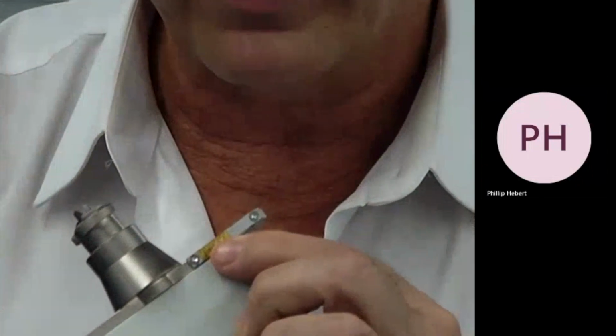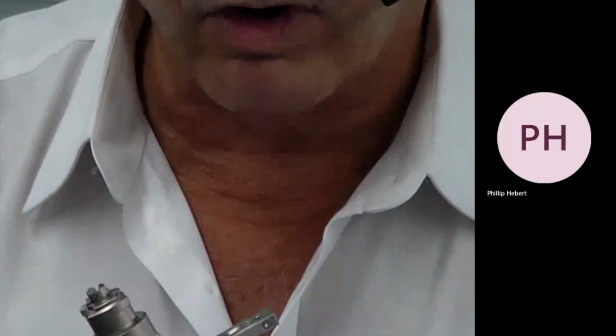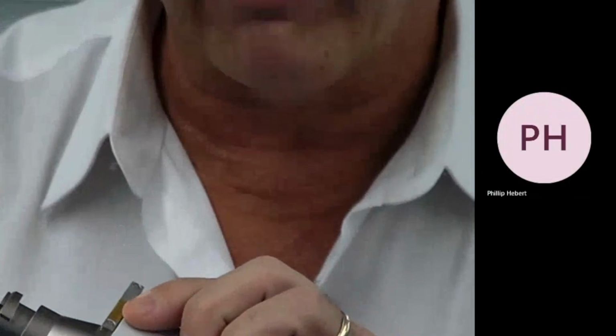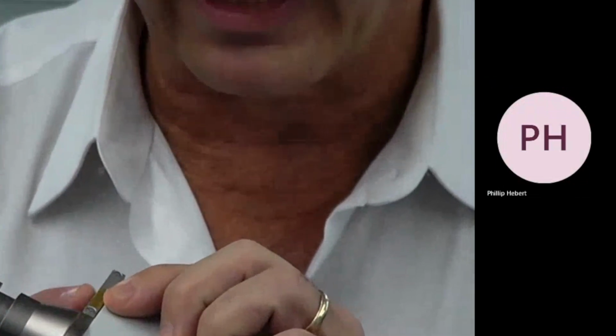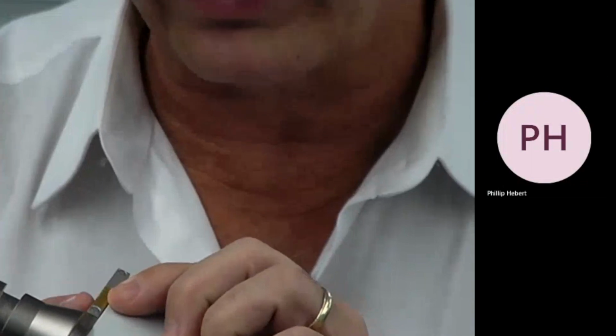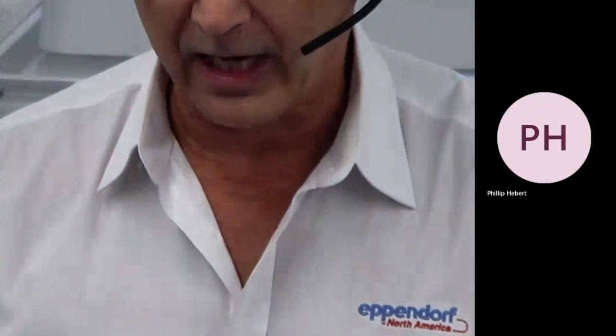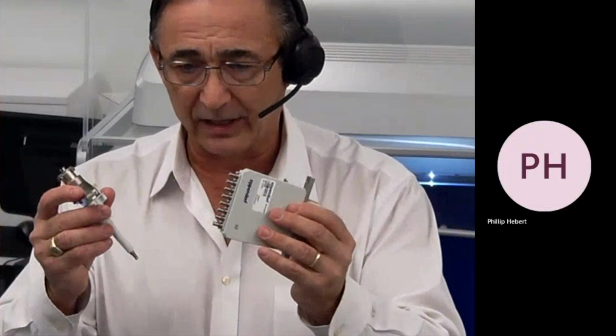And so it'll go and look at this. It will look here at the chips. There's little chips here. The chips actually identify the serial number of the tool, the last calibration date, and it keeps a running tally of the number of pipetting strokes since the last calibration date, and it will let you know if you are out of calibration. If you've gone more than a year or 200,000 pipetting strokes, it pops up with a message. You can bypass the message if you wish, but these are the essence of simplicity.